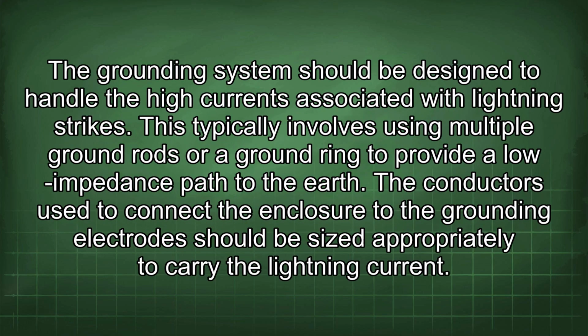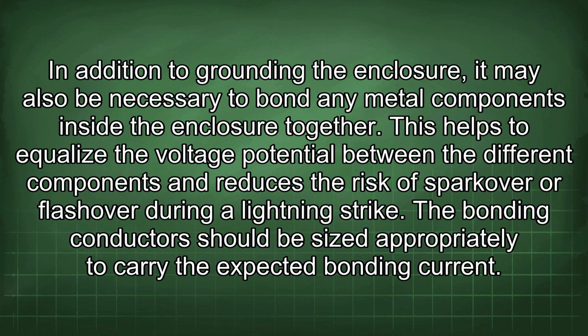of the strike. The grounding system should be designed to handle the high currents associated with lightning strikes. This typically involves using multiple ground rods or a ground ring to provide a low impedance path to the earth. The conductors used to connect the enclosure to the grounding electrode should be sized appropriately to carry the lightning current. In addition to grounding the enclosure, it may also be necessary to bond any metal components inside the enclosure together. This helps to equalize the voltage potential between the different components and reduces the risk of sparkover or flashover during a lightning strike. The bonding conductors should be sized appropriately to carry the expected bonding current.